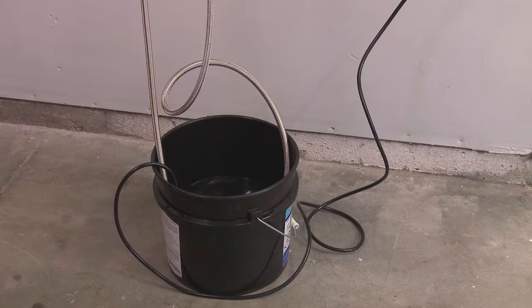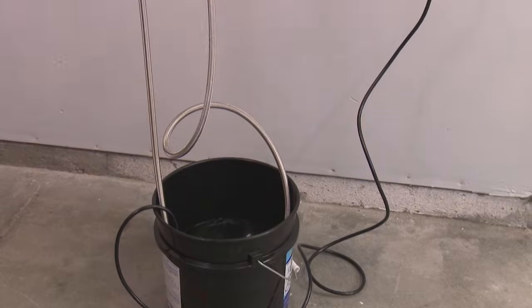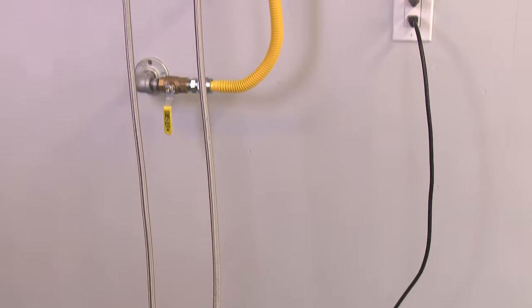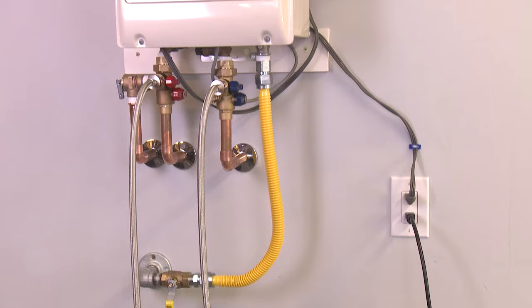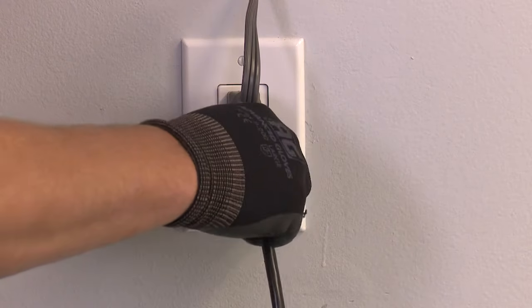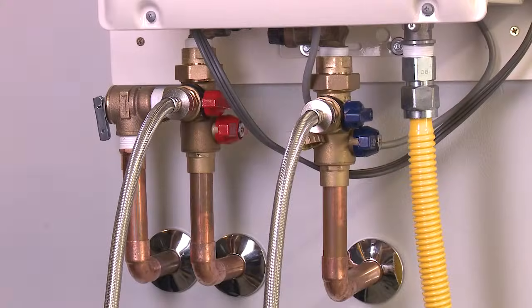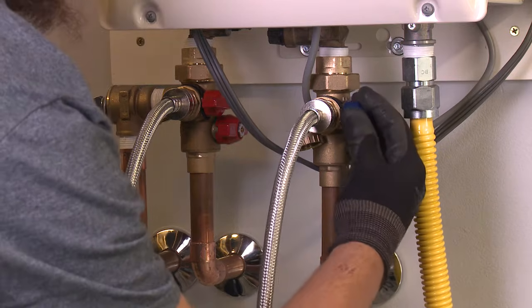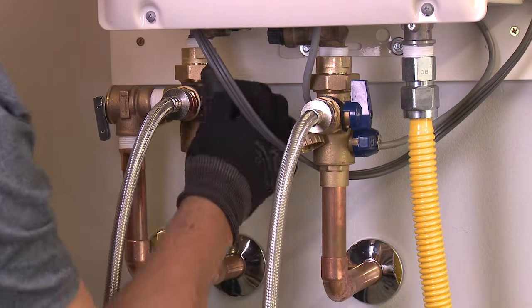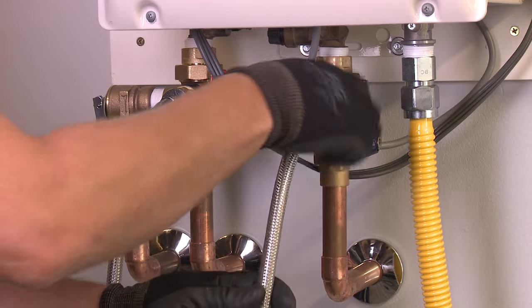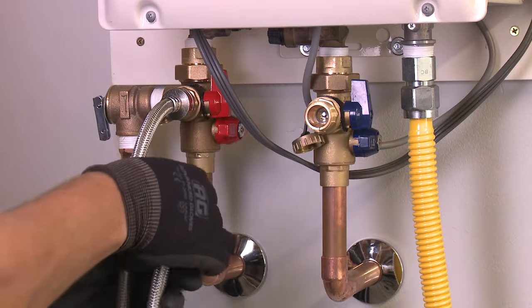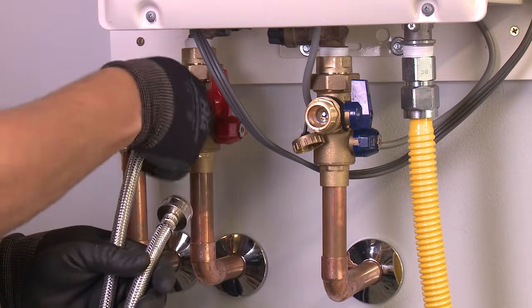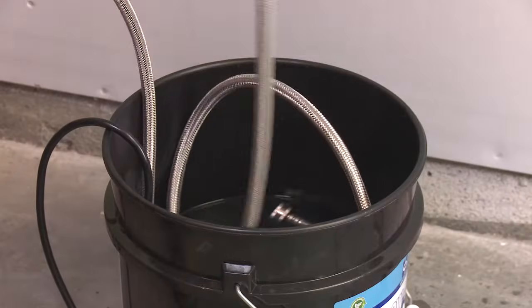Now that we've let our pump run for 30 to 45 minutes, we're going to disconnect power, drain the unit, and flush 10 to 20 gallons of fresh water through it. Now let's go ahead and disconnect our hoses. We'll close our drain valves, both hot and cold, and remove our hoses. And put our hoses in the bucket.